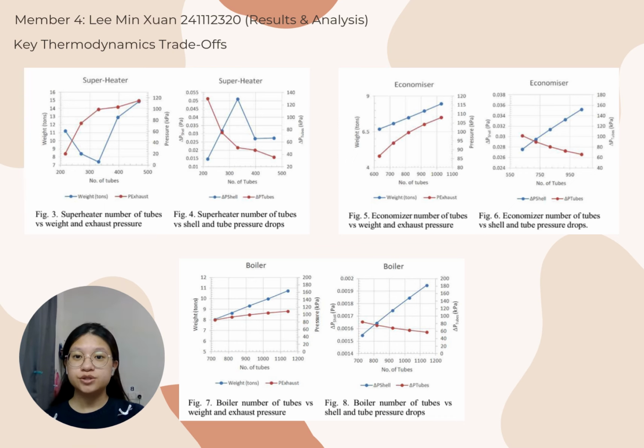For trade-off 1, tube count versus pressure. More tubes means lower tube side pressure drop, but more tubes also means higher shell side pressure drop. We balance this to keep total pressure acceptable. For trade-off 2, heat transfer versus size or weight. Designs that maximize heat transfer become impractically large and heavy. We found that sweet spot where performance meets practicality. For trade-off 3, thermal versus economic performance. The lightest designs were thermodynamically infeasible. The best thermal performance designs were economically prohibitive. We selected cost-effective designs that meet all technical requirements.